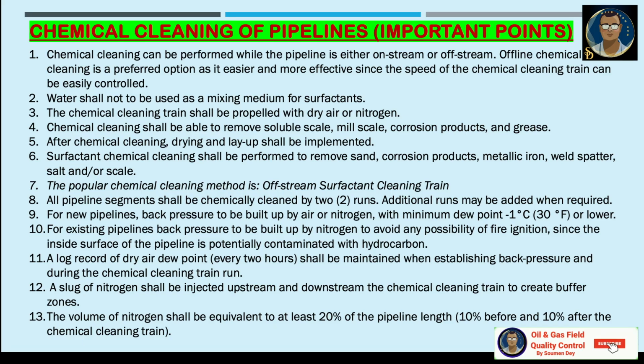For an existing pipeline, back pressure to be built up by nitrogen to avoid any possibility of fire ignition, since the inside surface of the pipeline is potentially contaminated with hydrocarbon. A log record of dry air dew point every 2 hours shall be maintained when establishing back pressure and during the chemical cleaning train run. A slug of nitrogen shall be injected upstream and downstream of the chemical cleaning train to create buffer zones. The volume of nitrogen shall be equivalent to at least 20% of the pipeline length, 10% before and 10% after the chemical cleaning train.